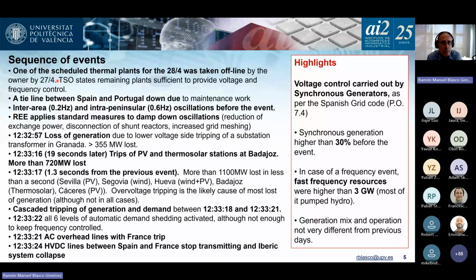Also, a big tie line between Spain and Portugal was down due to maintenance work. And during that day and in previous days, there were inter-area oscillations of 0.2 hertz, that's very well known, and intra-Iberic oscillation of 0.6 hertz, which is a kind of oscillation mode that has not been seen. Those were detected by the TSO, and the TSO started to apply the standard measures to damp down oscillations. The standard measures were reduction of exchange power with France, Portugal, and Morocco, disconnection of shunt reactors, and increased grid meshing.